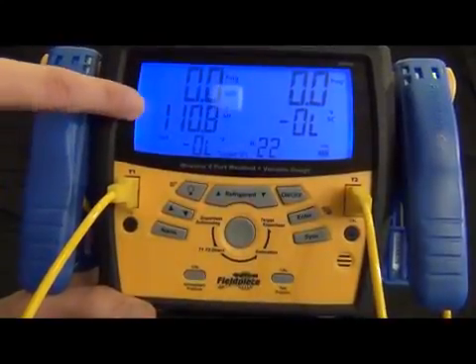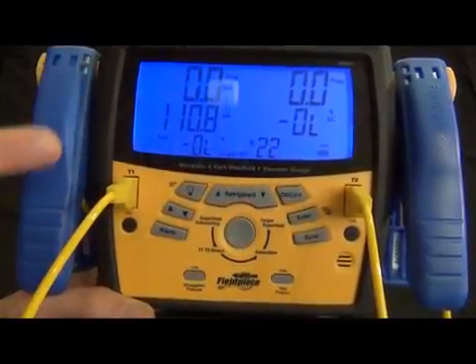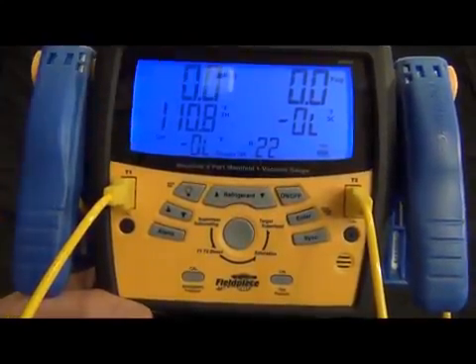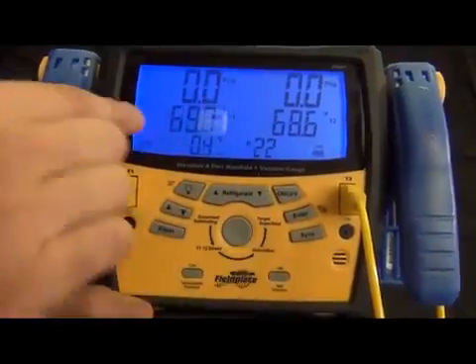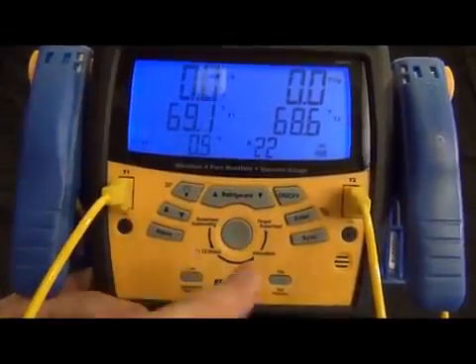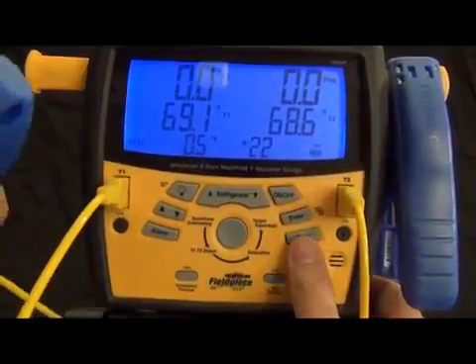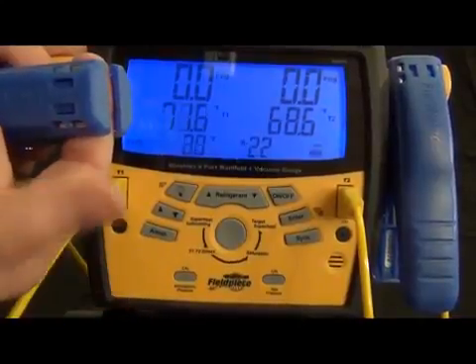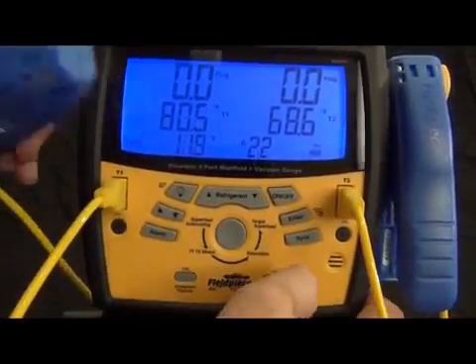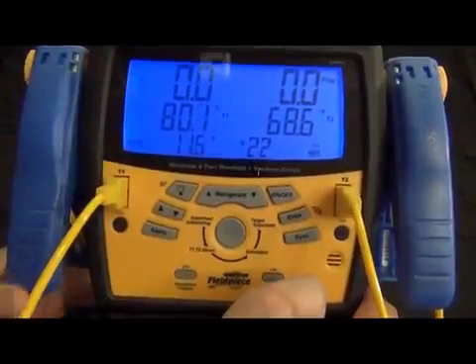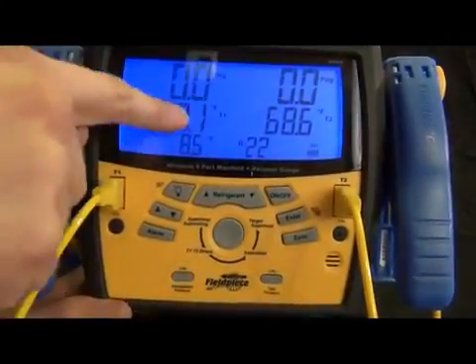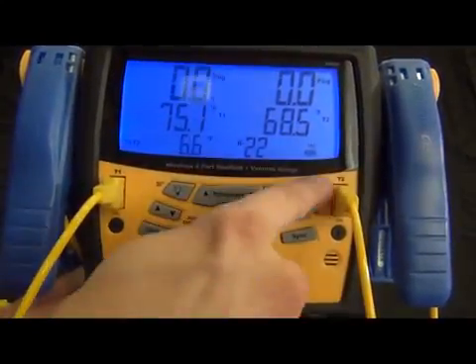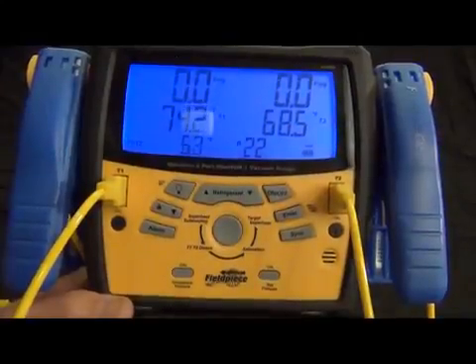So what this 110 degrees of superheat is saying is my pipe temperature of around 70 degrees and at zero psi produces a 110 degree superheat. To see that, the 69 degree temperature, that's the actual measurement this clamp is taking right here. So what I can do is just show you how it creeps up. I'll just warm it up a little bit with my finger and you can see it climb really fast. And so T1 is always to this port right here, left side of the left clamp. And then T2 is displayed right here and it always will be your right clamp.